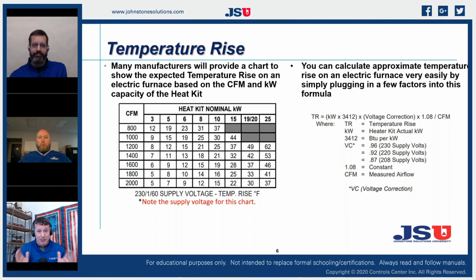We want our heat exchangers to last, right? So we put that temperature rise at 35 to 55 degrees or so. An electric furnace is actually similar in that temperature rise. We typically are going to be 30 to 40 degrees temperature rise on an electric furnace. So when we're checking an electric furnace, we want to make sure that we check that temperature rise. We want to know what the actual temperature is on that. We could also calculate that again if we really wanted to.